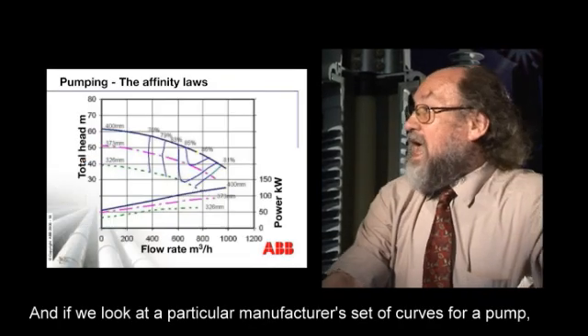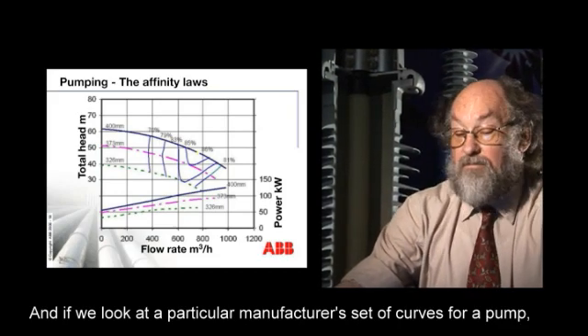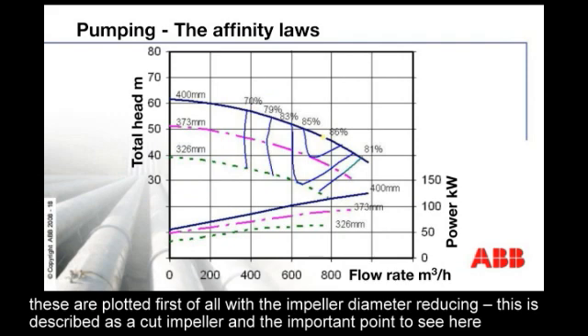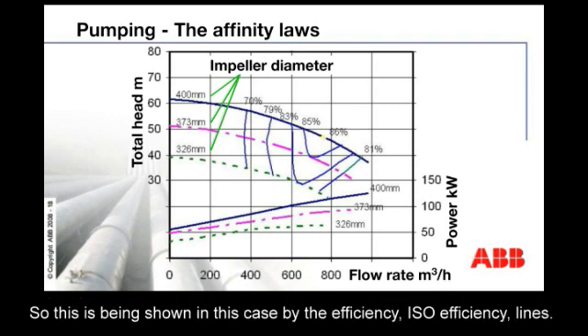Looking at a particular manufacturer's set of curves for a pump, these are plotted first with the impeller diameter reducing — described as a cut impeller. The important point is that the flow-head-volume curves all decline, but the efficiency curves actually tend to reduce as the impeller cut increases, as shown by the ISO efficiency lines.